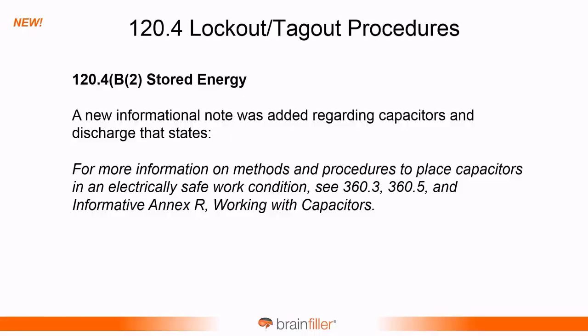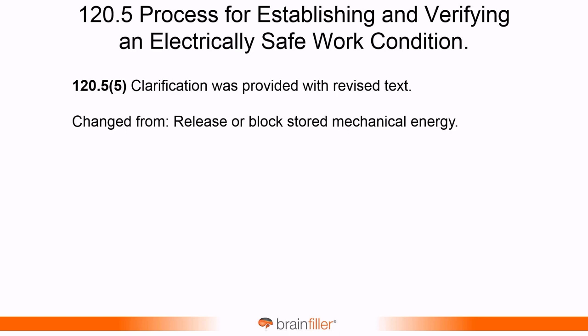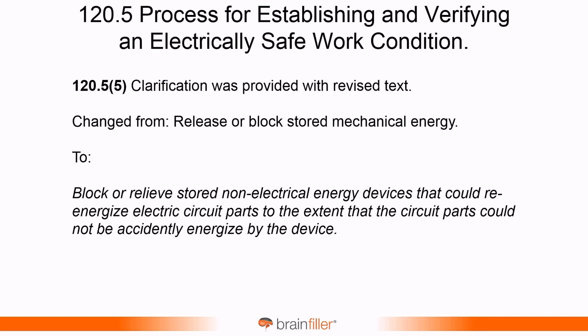This is a new reference to the new Article 360 and Annex R when it comes to releasing stored energy of capacitors. Similarly, the process of establishing and verifying an electrically safe work condition has releasing mechanical energy. And the way this read originally from 2018, "release or block stored mechanical energy." That's kind of a broad term. Mechanical energy? I mean, that could be a lot of things out there. So this was tightened up a little bit, and the new and improved version of it is "block or relieve stored non-electrical energy devices that could re-energize electric circuit parts to the extent that the circuit parts could not be accidentally energized by the device." So this is now focusing on the electrical system.